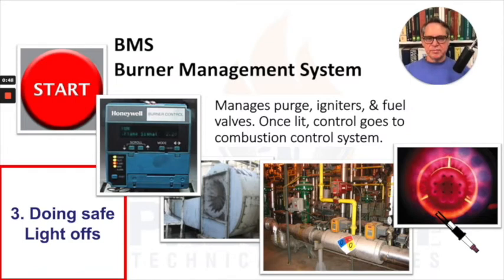Now this is with some type of forced draft, balanced draft, or induced draft system. Of course, in a natural draft system, there's no fan to start. So once we prove that we've got the proper amount of purge air, a timer goes off on the burner management system. We then get to the point where the firebox is deemed purged. We then open, through some special sequencing, the main safety shutoff valve, blocking valve system. We would light a pilot first, most likely, then light the main flame. So I'm going to take you through all of this step by step and show you a lot of details about each step.